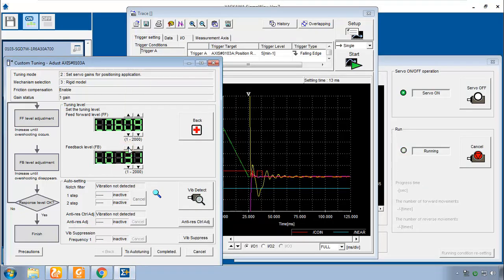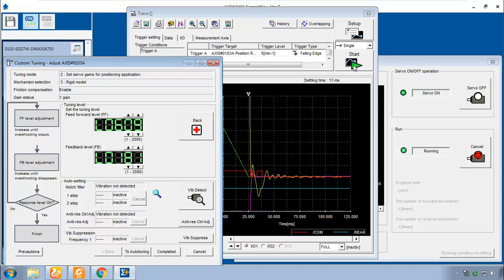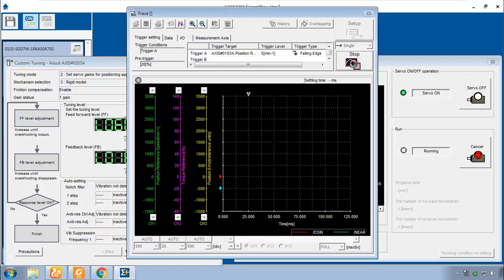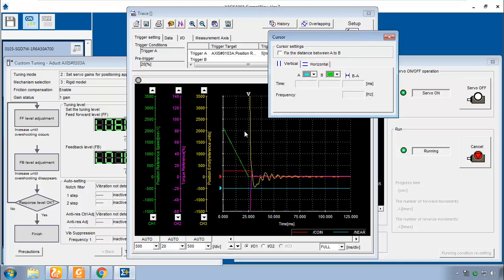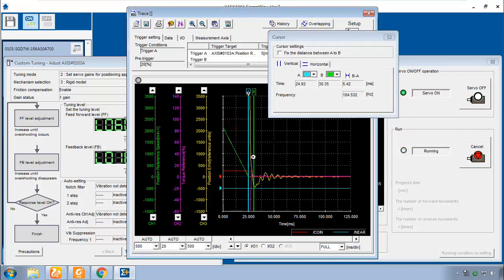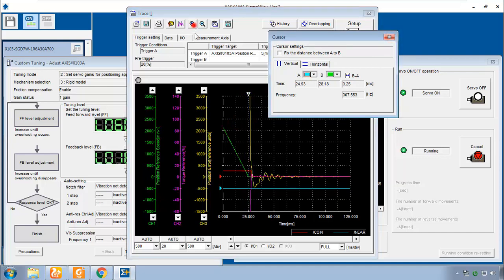Go by tens. And you can hear that the motor's becoming more aggressive in its moves. And let's take a trace now. And you see, now the settling time has come down to three milliseconds because we're staying here below four hundred sixty six pulses worth of error from this point on. Measure that real quick here. Yeah, just a little over three milliseconds. Probably should zoom in if you want to be real accurate.